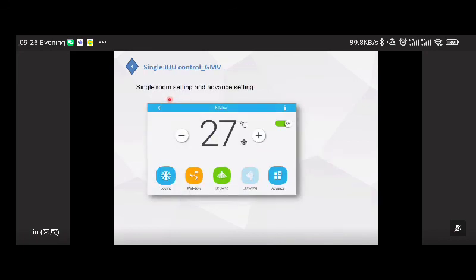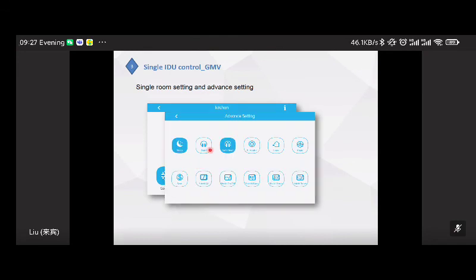Okay, and this is a choice for your selection. And this is the setting for one unit. Temperature change, running mode, fan speed, and swing. And advanced. Here are more settings you can find. Press the advanced, and you can see the sleep, quiet, e-heater, absence, and some shield operation here. This part is very useful for the central controller management to shield some operation on the wired controller, especially for some apartment and office to avoid the operation by the other people.